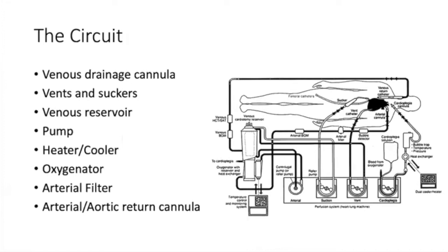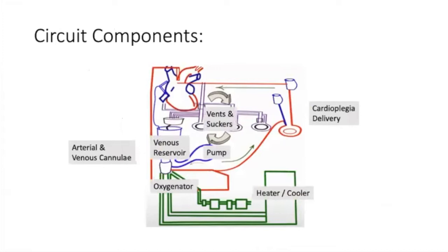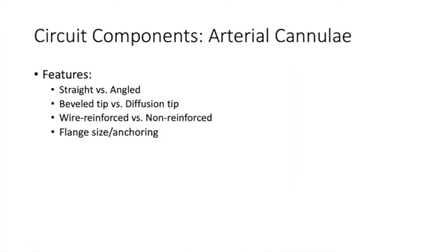The circuit is frequently shown in complex diagrams, so we'll break it down using a simplified version. The key components are your cannulae, your venous reservoir, your oxygenator, and your pump — those are the basics. We'll then add on cardioplegia delivery, vents and suckers, and the heater-cooler paired with the oxygenator. From a simplicity standpoint, the most basic aspects are your arterial and venous cannulae, the pump itself, and the oxygenator.